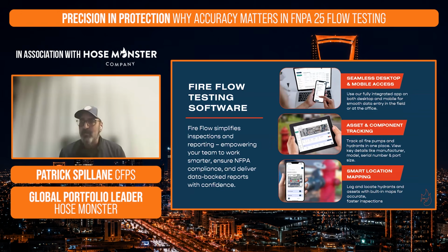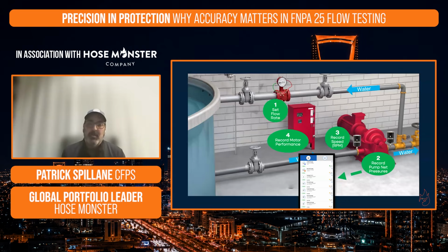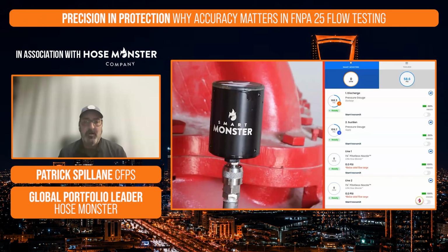And then the great thing about it is that when you go back to these job sites year after year, you can see the previous year's data and compare and benchmark. So as I was showing earlier with our fire pump room here, now that we have Smart Monsters set up on the suction and discharge side of our fire pump, we're going to be able to get that data directly into that mobile app to see exactly what's going on with that fire pump throughout our test. So once we set our flow rate, we're going to be able to screenshot that and document our data. Or the great thing about that is that we're going to be able to bring the data directly into the software.